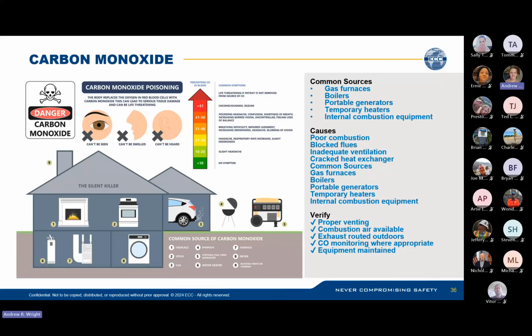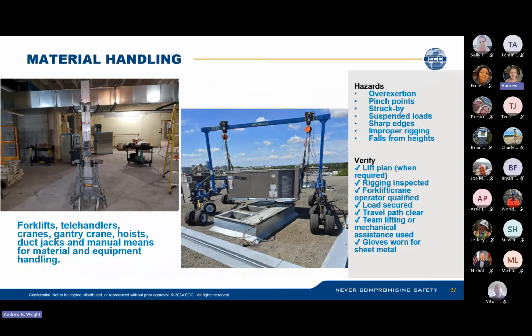Material handling. So when you guys are installing new systems or replacing components, you're going to have to handle some material, and that comes with its own hazards, right? So that's your forklifts. You're going to use forklifts, telehandlers, a crane if it's a large rooftop unit or something like that, a gantry crane, which is the picture in the middle to the right, maybe a duct jack, which is the picture on the far left. These are all means for installing and handling the equipment. So your hazards are typical with most material handling jobs. It's overexertion if you're picking up stuff by hand, pinch points and struck by if you're using equipment, load handling equipment, suspended loads, sharp edges, improper rigging, and falls from heights.